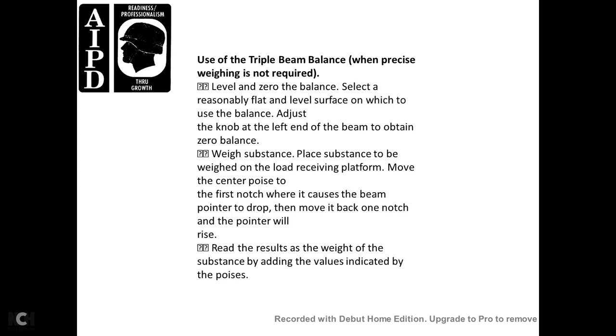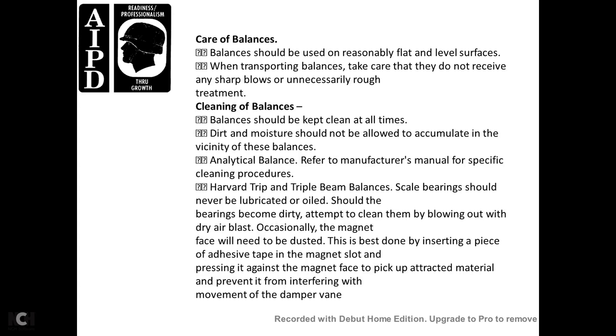Using the Triple Beam Balance when precise weighing is not required: level and zero the balance by selecting a flat and level surface; adjust the knob at the left end of the beam to obtain zero balance. Place the substance to be weighed on the load-receiving platform. Move the center poise to the first notch until the main pointer drops; move it back one notch so the pointer will rise. Read the results as the weight by adding the values indicated by each poise.